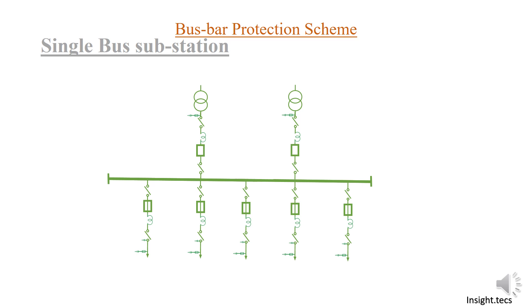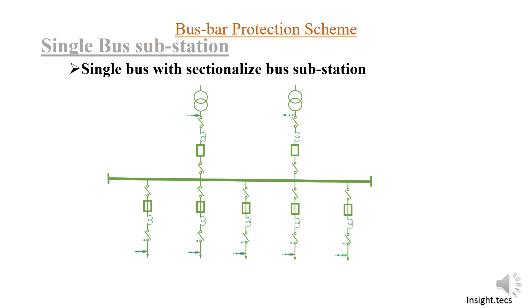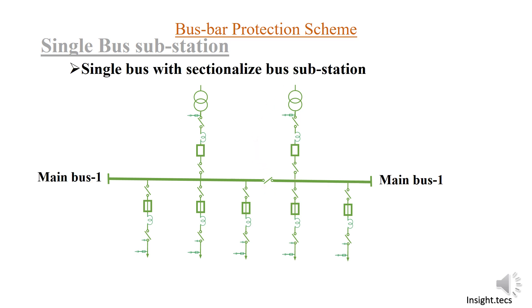The other type of single bus substation is the single bus with a sectionalized bus substation. The difference here is that an isolator or a circuit breaker is kept in between, providing a section in the main bus itself. It is the same bus but now having two sections. In order to do maintenance, you can open this isolator and isolate both bus sections, so the total substation will not lose power. You can do maintenance of the bus in two sections, and this is the single bus with the sectionalized isolator.